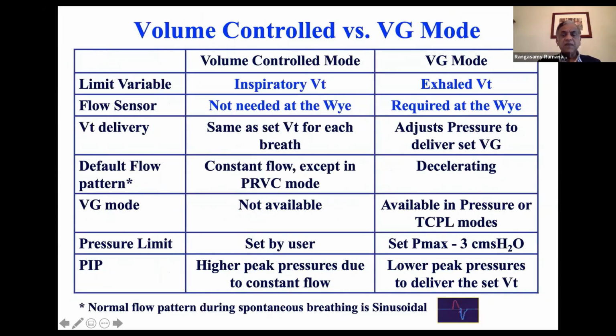So here is the major confusion. Sometimes people get confused. What is the difference between volume control mode or volume targeted mode and volume guarantee mode? This is the most important slide I want you to remember. In volume control mode, you control the inspiratory tidal volume. In volume guarantee mode, you control the expiratory tidal volume coming out of the baby. Flow sensor: you don't have to have one at the Y, between the endotracheal tube and the circuit, whereas in volume guarantee mode, you have to have one at the Y.